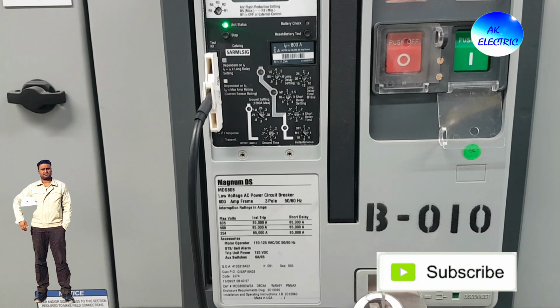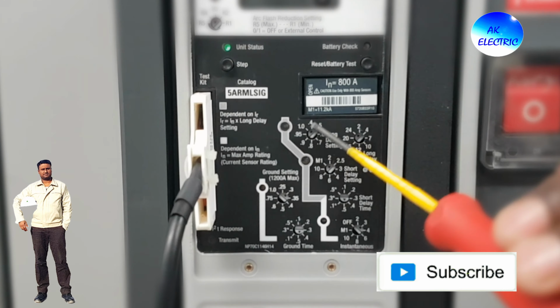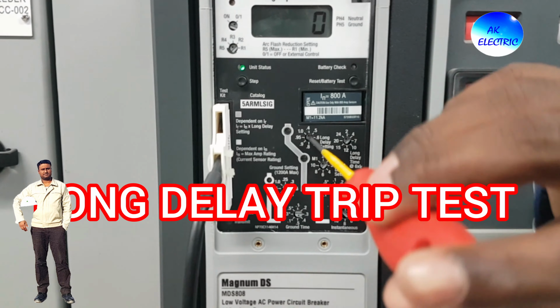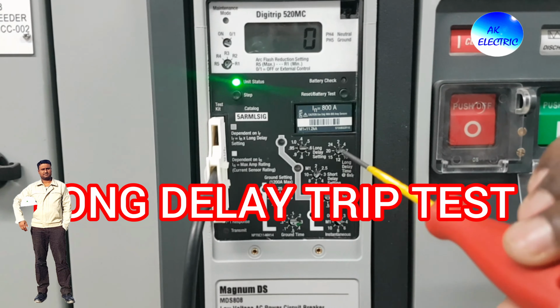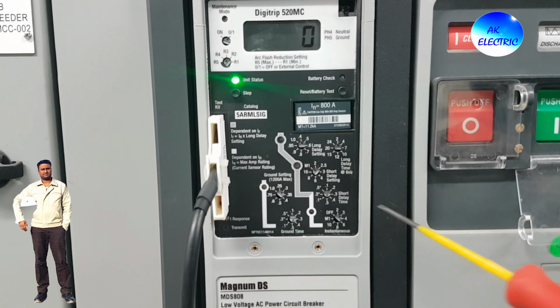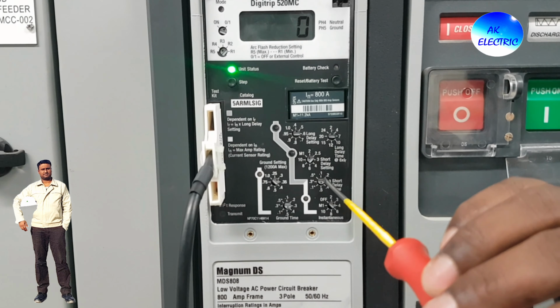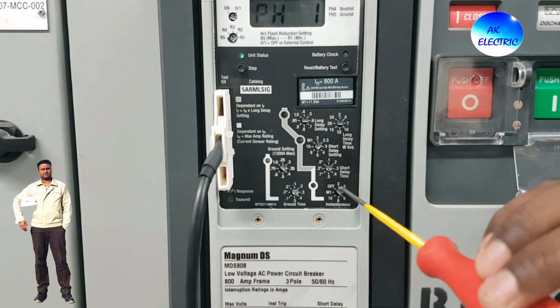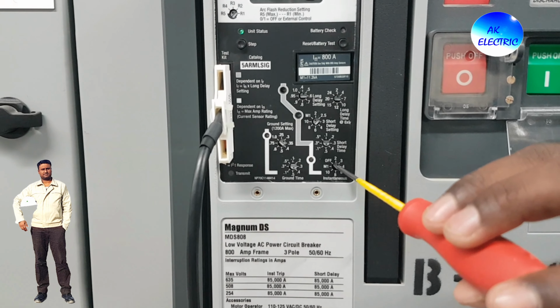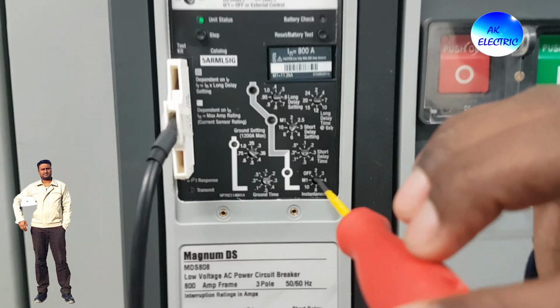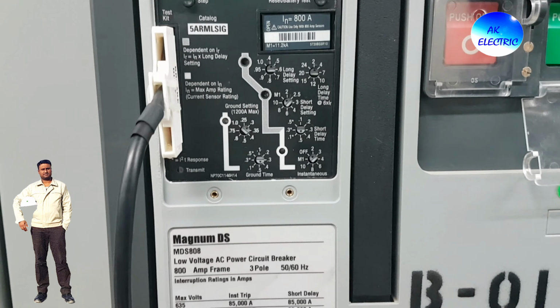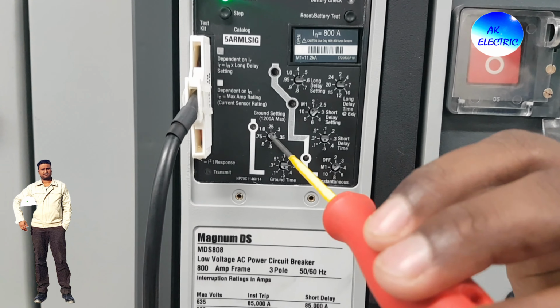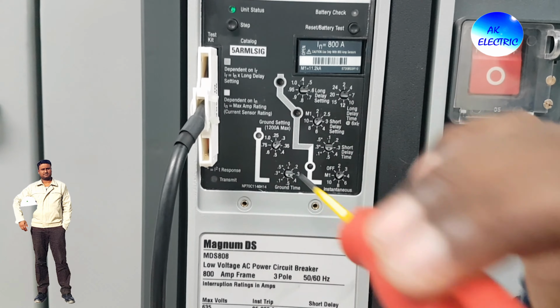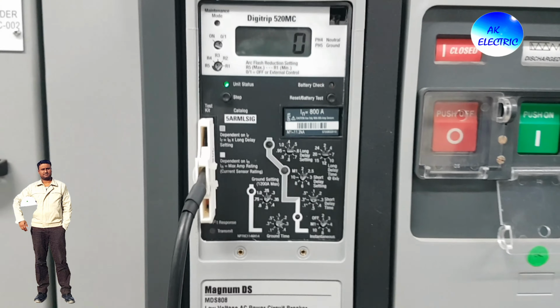Okay, now long delay 0.4 set, 0.4. Okay, time 2. Okay, short delay maximum M1. Okay, and 0.5 here. Okay, and here put instantaneous off. Okay, and ground fault maximum 1, and timing 0.5. Okay.